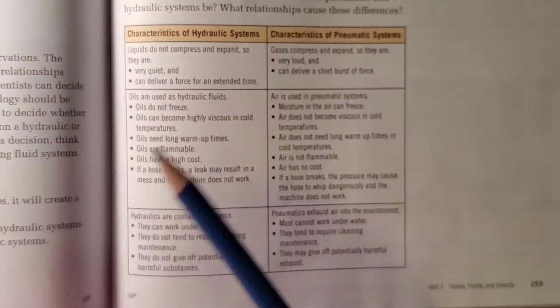So let's just look at this chart on page 255 that compares the two systems. There's hydraulic systems and there's pneumatic systems. Which one is better? Well, it kind of depends what it's going to be used for. Hydraulic systems are on the left, pneumatic on the right. Liquid filled, gas filled, okay? Liquids do not compress and expand, so they are very quiet and can deliver a force for an extended time. The gases tend to sometimes seep out in some cases. They're loud as they bring in and compress, and they can deliver a short burst of force, but for sustained time, it doesn't work so well. So if you need to hold something for a long time, hydraulic is going to be better, whereas if it's a quick thing, for example, maybe a jackhammer, a pneumatic system might be a lot better.